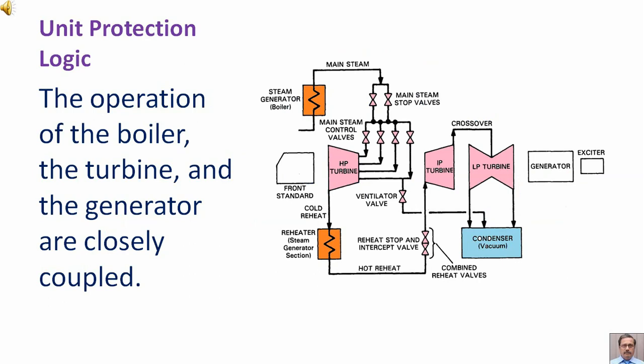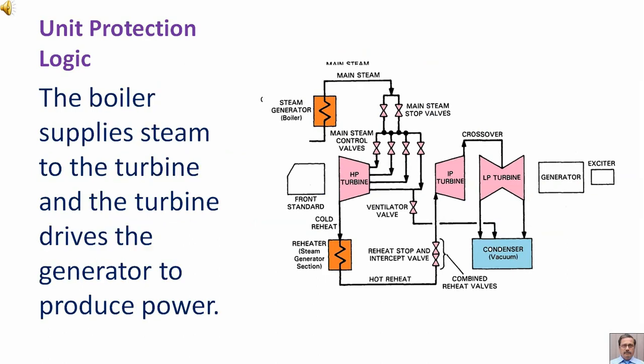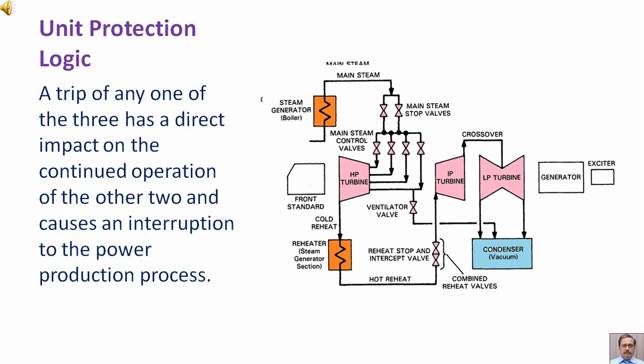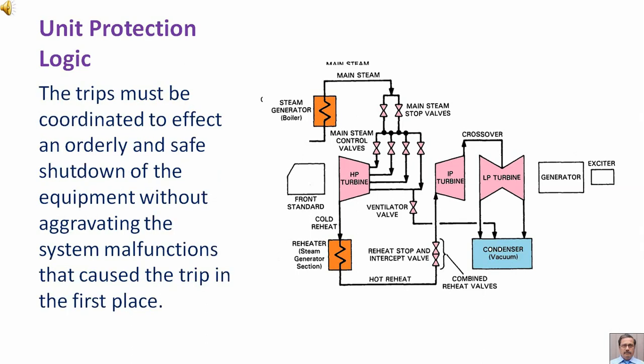The operation of the boiler, the turbine, and the generator are closely coupled. The boiler supplies steam to the turbine and the turbine drives the generator to produce power. A trip of any one of the three has a direct impact on the continued operation of the other two and causes an interruption to the power production process. The trips must be coordinated to effect an orderly and safe shutdown without aggravating the system malfunctions that caused the trip in the first place.